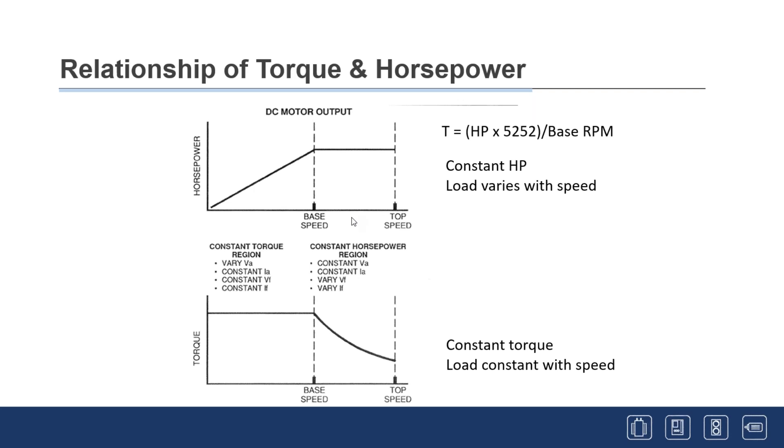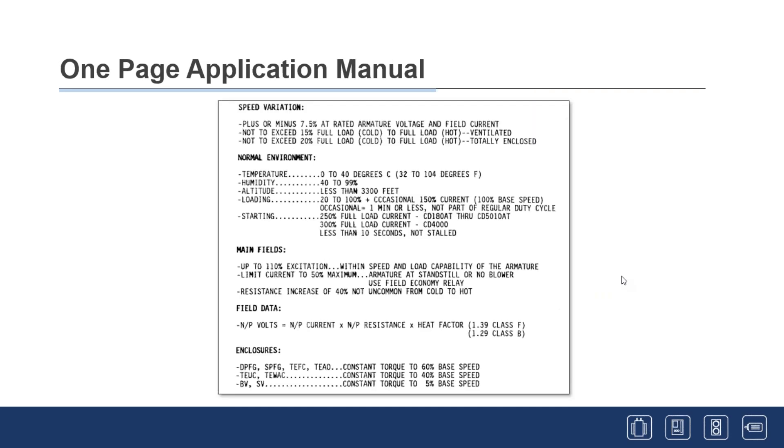The DC motor performance curve shows constant torque from zero speed to base speed — the nameplate base speed. Constant horsepower operation is where load varies with speed, typically used for winders and drums. Constant torque is where the load is constant with speed; you run those motors from zero up to base speed, then you lose torque as you have to weaken the field to go faster. Most of those motors are run in the constant torque range.